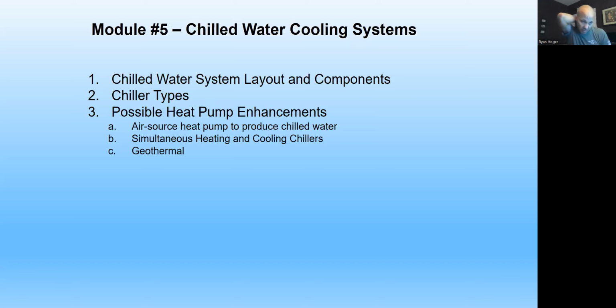So we'll do a little bit of discussion about chilled water systems and what they are, not nearly as much as we did on the heating side, because honestly, from a hydraulic perspective, boiler systems and chiller systems are the same thing. Moving water around a building, right? So you have all the same things we talked about last module. You have expansion tanks, circulating pumps, air separators, all that stuff exists with the same kind of logic to it. But obviously, we're making cold water in this case. And there are several different ways that we can make these into various kinds of heat pump systems.